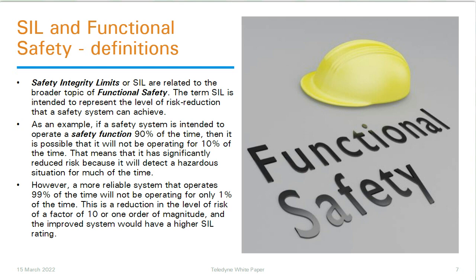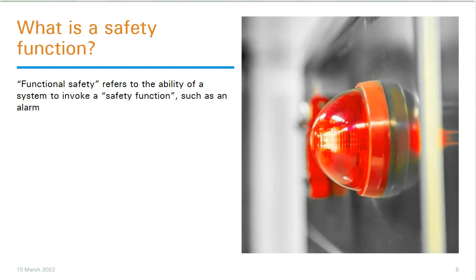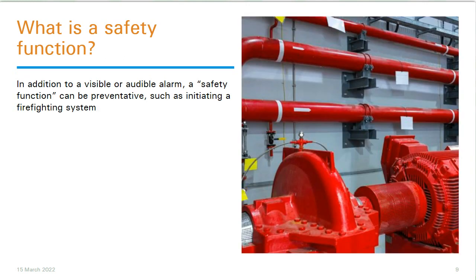So what is a safety function? Well, functional safety refers to the ability of a system to invoke a safety function. That's what it's all about. And a safety function might be something like an alarm, an audible or a visible alarm, a flashing red light, or a siren working in the factory. Another example, a safety function could initiate, for example, a firefighting pump. It could start the pump to make sure that the firefighting system is pressurized with water ready to be used. Not necessarily initiating water sprinklers, but simply starting the pump to make sure that the system is pressurized and ready. It could, of course, go one step further and initiate a sprinkler system.